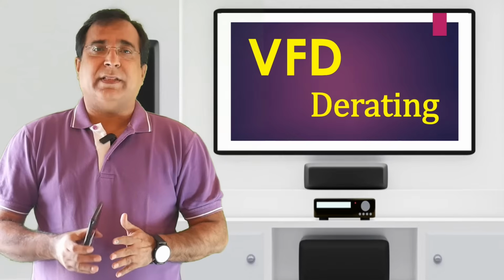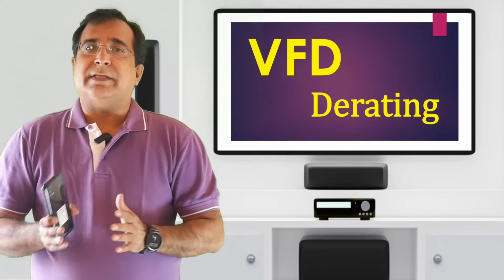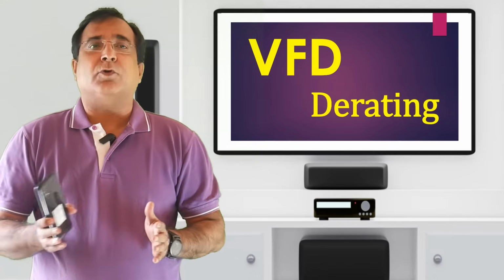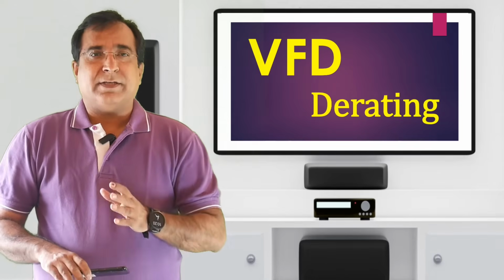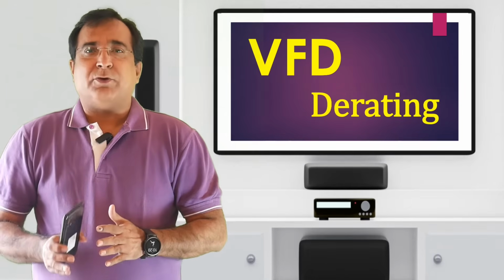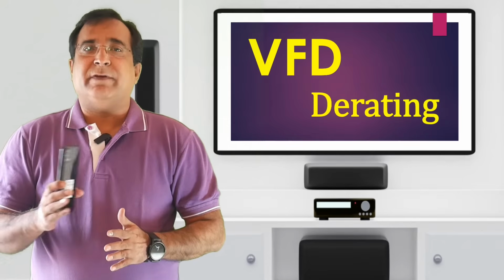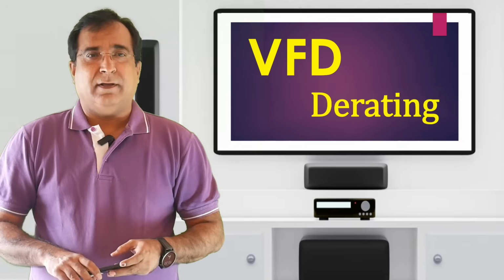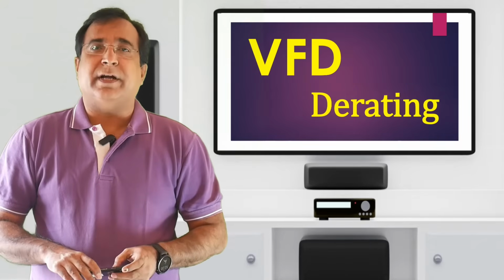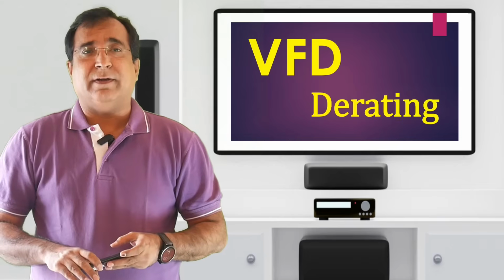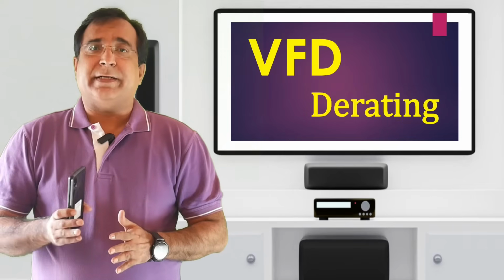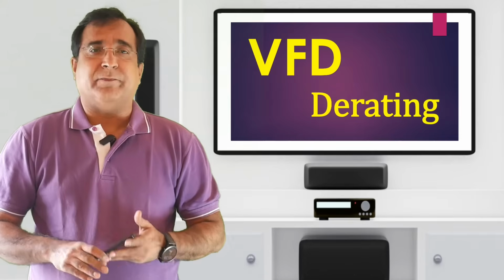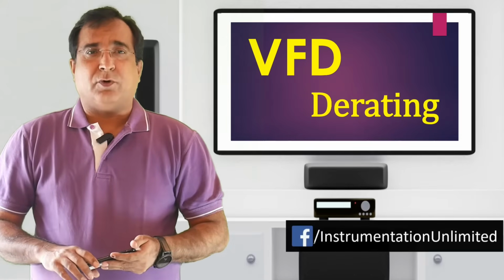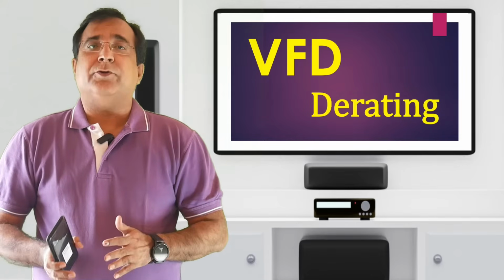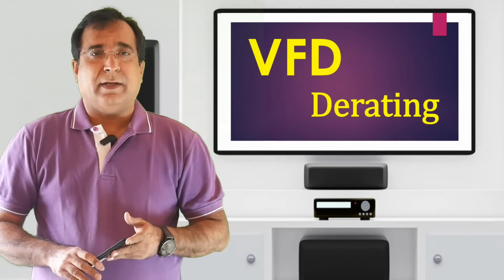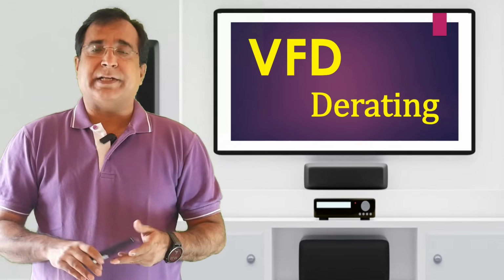I mean, if the motor and the VFD both are operated in the same relative environment, then there is no need to derate the VFD. Let's understand this phenomenon. Suppose a 10 HP motor and corresponding VFD both working well at sea level. If say motor and VFD are taken to 10,000 feet above sea level, then both of them get derated together on their full current rating. So there is no need to change the motor and VFD. Both will continue to work at a slightly reduced capacity because the environment of both has changed relatively.